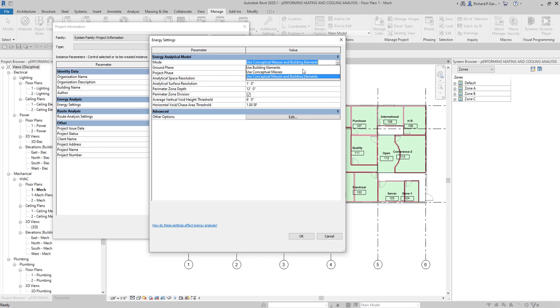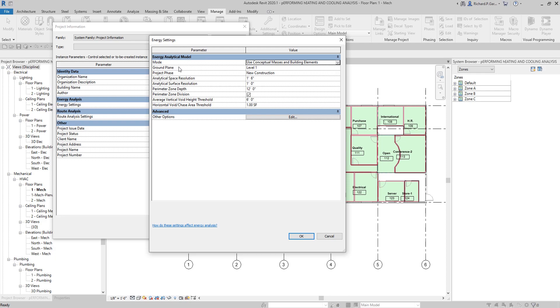The other options — 'Use Building Elements' and 'Use Conceptual Masses' — relate to legacy behavior and are provided only to support older models. Some advanced energy settings relate only to these legacy modes. Another parameter is Ground Plane, where you can specify the level below which the energy model surface is assumed to be in contact with the ground for heat transfer. I'll use Level 1 here. For the Project Phase, all building elements assigned to the specified phase or an earlier phase are included in the energy analysis. I'll use the New Construction phase.